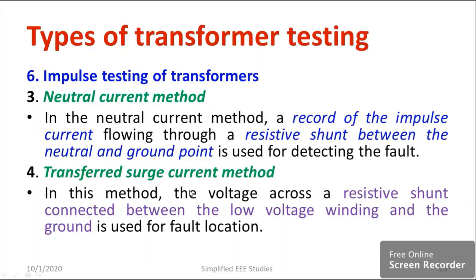Moving on to the transfer surge current method — it is similar to the neutral current method. In this method, the voltage across a resistive shunt connected between the low voltage winding and the ground is used for fault detection. In the neutral current method we measure current, while in this method we check the voltage across the shunt between the low voltage winding and ground. These are the different procedures under impulse testing of transformers.